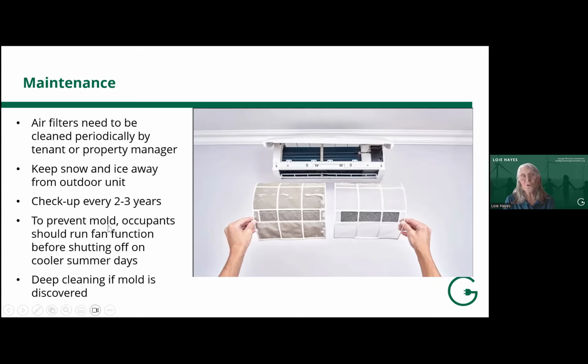To prevent mold, you want to tell occupants that in the shoulder seasons, spring and fall, when you use the heat pump some days and turn it off other days, you should run the fan for a period when turning it off until the inside of the machine comes up to room temperature and the moisture is wicked away. This prevents condensation being left in the machine when you turn it off on a nice day and open the windows.